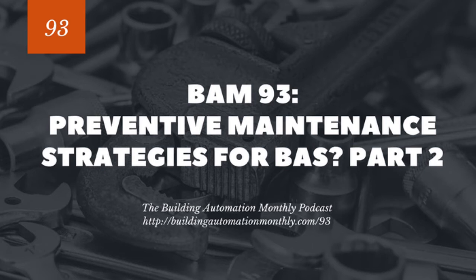So this would be another good check, especially if you take over a building or if you start servicing a building. I would go through and check these things, because chances are you're going to run into at least some duplicate instance numbers. And also, this goes, I've got to stop making these statements. I keep going, it goes without saying, or everyone knows. I'm like, no, Phil, everyone doesn't know. But it's important to say that the BACnet broadcast management devices, or BBMDs, need to be set up properly as well. Now, remember, BACnet is a broadcast protocol, meaning that it sends traffic out on all ports of the local area network.